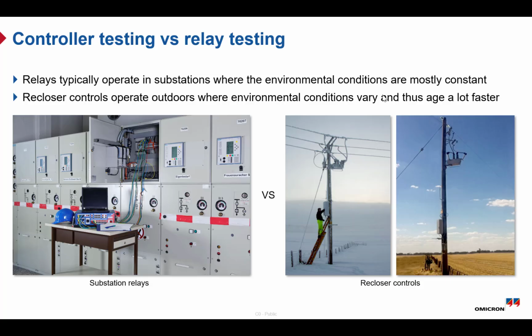In a substation, protection relays are installed in a controlled environment. Conditions are stable and you usually have enough time and space to set up your test equipment and connections. You can connect through test switches or terminal blocks and perform testing in a structured way.